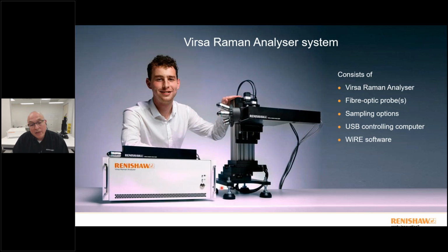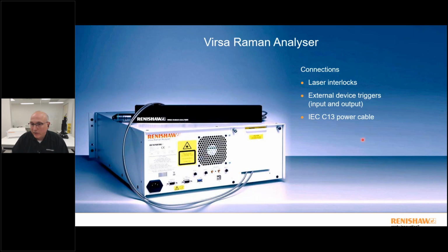The unit itself comes with the Virsa Analyzer, and then you use some sort of fiber optic probe, some sampling options. It's a simple USB connection to a laptop or PC, and then it's using the same WiRE software that we're using on our Renishaw inVia Raman microscope systems. So that's complete with all the data processing and data analysis tools that you could ever want, plus all the additional reporting functionality. On the back end, you're going to see laser interlocks, trigger inputs, and then it's just standard 110 volts if you're in the US market. But it's voltage sensing, so it'll adapt to anywhere between 90 and 240 volts. So it's a very simple system to integrate.